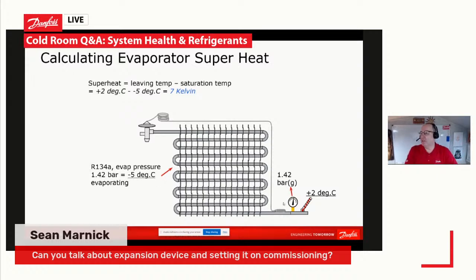Now, we measure with a temperature probe on the outlet of the evaporator, and we can see there we are reading +2 degrees C. That means we have 7K superheat on our evaporator, and 7K, 8K is about where we want to be. Don't go much lower than about 6 Kelvin. We don't want to risk getting liquid back to our machine. We don't want something as high as 10, 12 Kelvin on our evaporator, because then we're not utilizing the surface area of our evaporator.